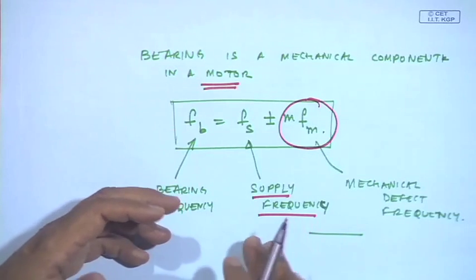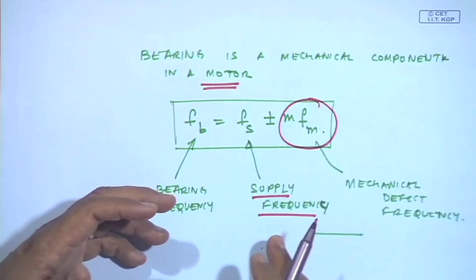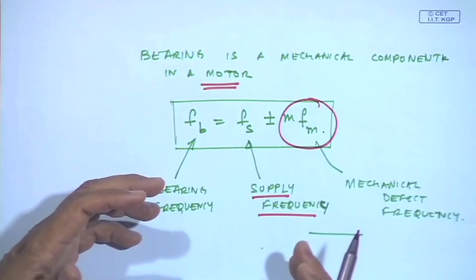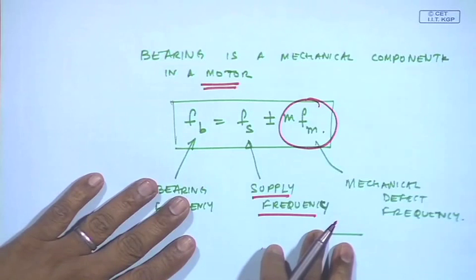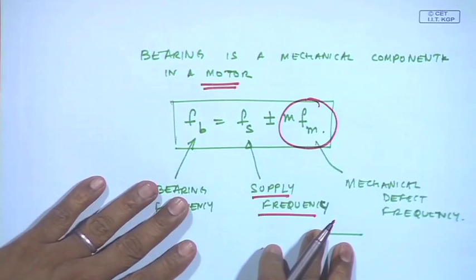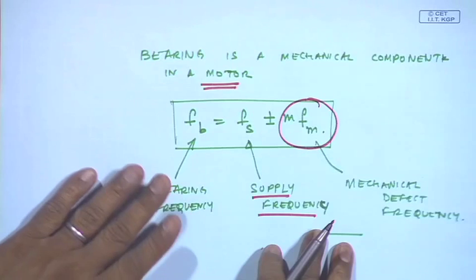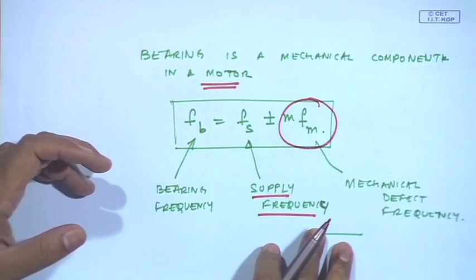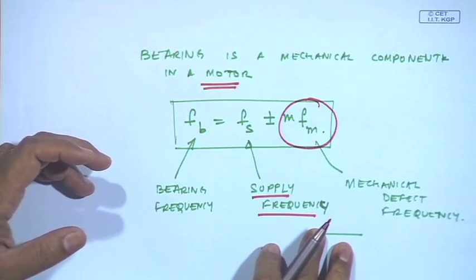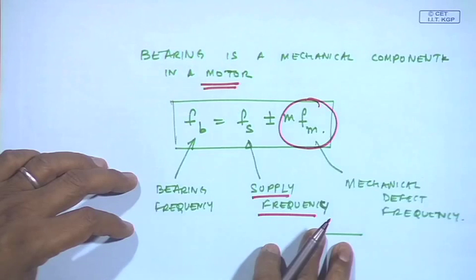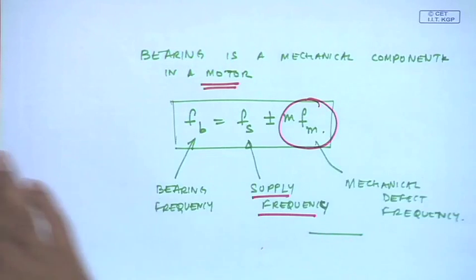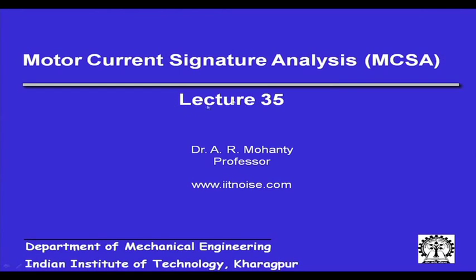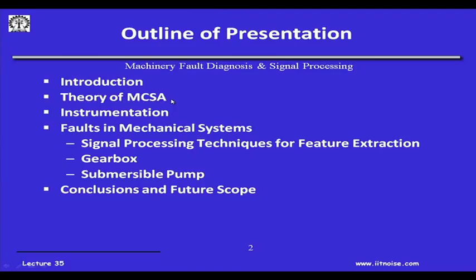We will see the genesis of how this happens in an electrical motor and you will see how powerful this technique is, for the fact that it is non-intrusive. I need not go near the mechanical unit. Remotely, at my control room, just by accessing the conductors carrying the current of the electrical motor, I can find out the faults. In this lecture on motor current signature analysis, I will basically tell you about the theory of MCSA.